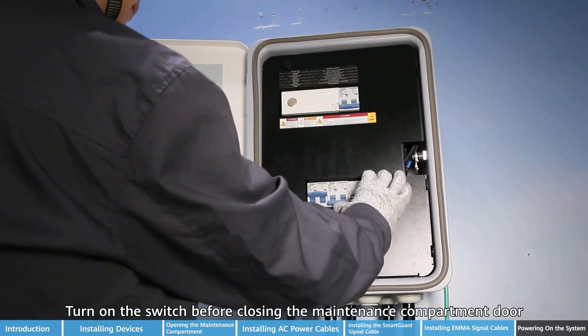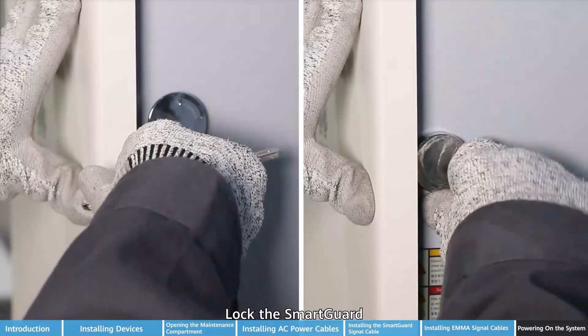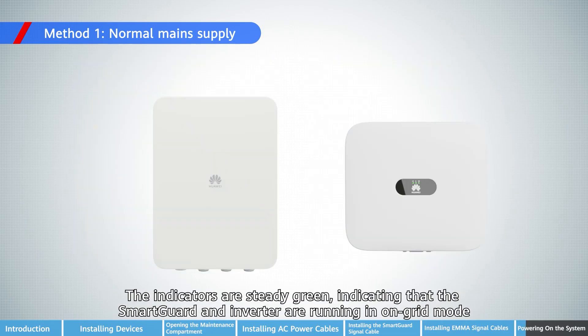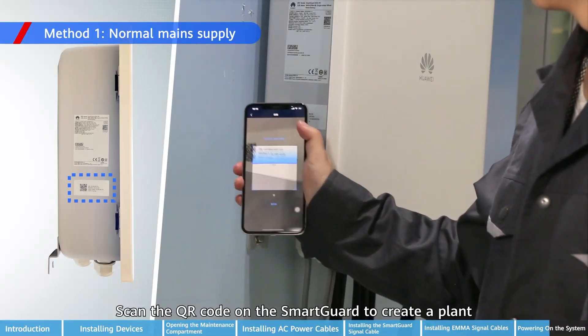Turn on the switch before closing the maintenance compartment door. Close the door of the maintenance compartment and lock the SmartGuard. The SmartGuard is powered on with normal main supply. The indicators are steady green, indicating that the SmartGuard and inverter are running in on-grid mode. Power on loads. Scan the QR code on the SmartGuard to create a plant.